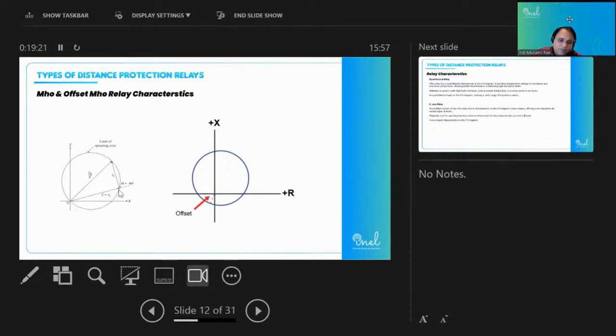Its reach depends upon the angle. At that angle, the length of this line, or the reach of this relay, will be smaller. But if the angle is increased, then its length, its reach, will also increase. So this is dynamic in nature. If a fault occurs at this angle, then its reach is this one. But if a fault occurs at this angle, then its reach will automatically get increased. So this is the Mho relay.